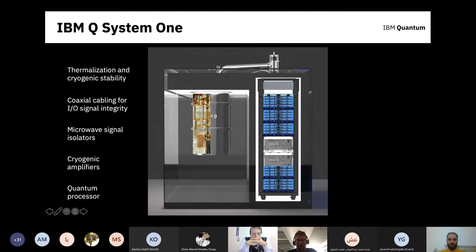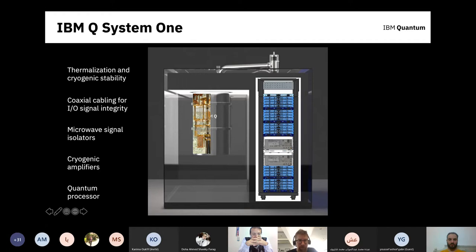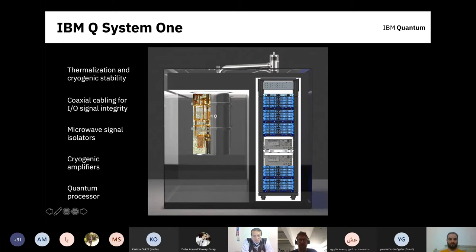To get extremely cold, you need to start very cold. We now have dry systems that start the cooling with electricity only. Everything gets colder as you go down through the plates, from warm at the top to cold at the bottom — that's where all the quantum hardware lives. Using a pulse tube compressor, we can get the top plate to 50 Kelvin and the second plate to 3 Kelvin, using just a closed cycle of helium-4 in a closed loop — no liquid helium needed, just electricity.